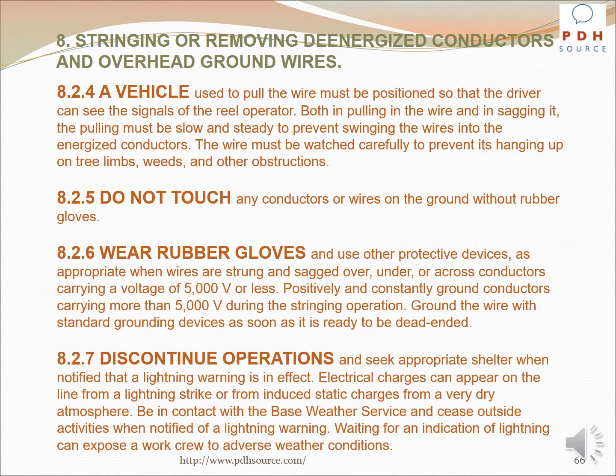A vehicle used to pull a wire must be positioned so that the driver can see the signals of the reel operator. Both in pulling in the wire and in sagging it, the pulling must be slow and steady to prevent swinging the wires into the energized conductors. The wire must be watched carefully to prevent its hanging up on tree limbs, weeds, and other obstructions.